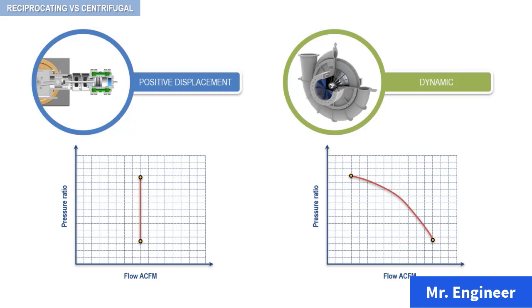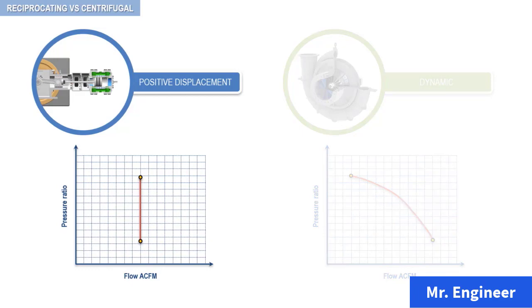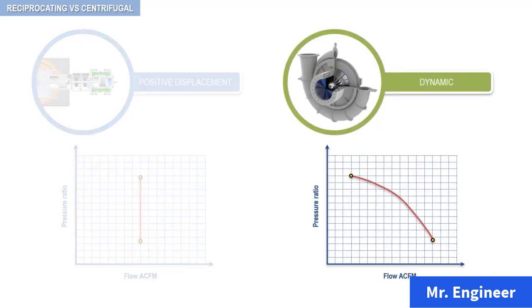Now, before finishing this video, what I really want you to understand and keep in mind is that reciprocating compressors are not self-limiting. This means that the discharge pressure will continue to rise until the compressor maximum case pressure is exceeded. On the other hand, centrifugal compressors are self-limiting. Their performance curves, as depicted here, show a decreasing head or pressure with increasing flow.